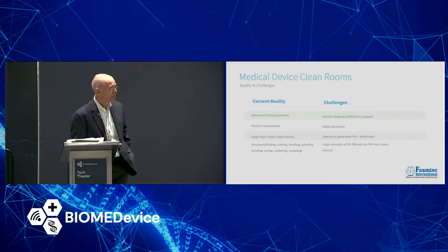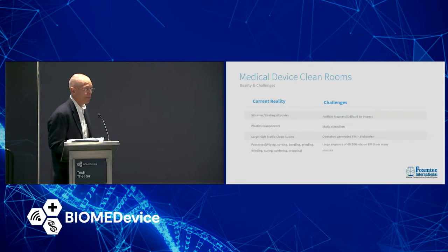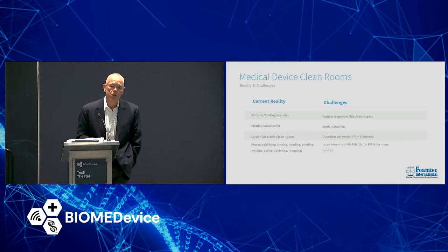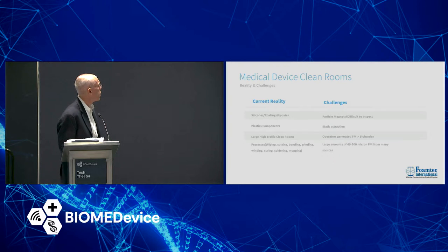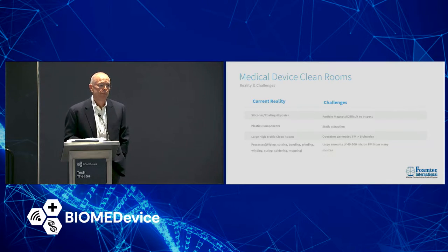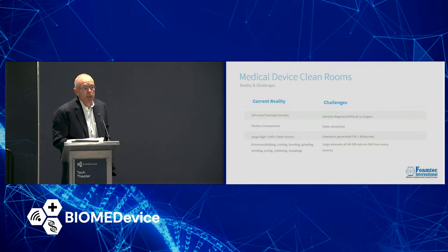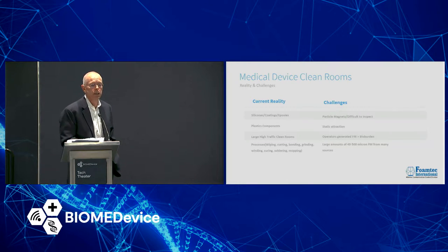So let's talk about some of the different scenarios that we run into. Obviously, when we're dealing with silicones or lubricious coatings or epoxies, FM is even more insidious because the devices are a magnet for particles, and the particulate can become embedded or worse, semi-embedded in the device, leading to expensive rejects. Very difficult to rework that. A lot of our components are plastic, so there's a static attraction aspect to it.